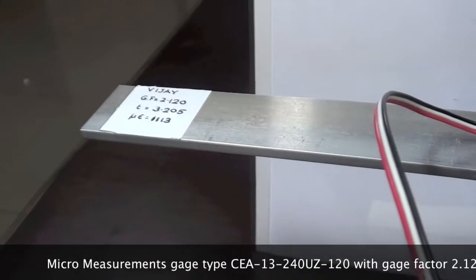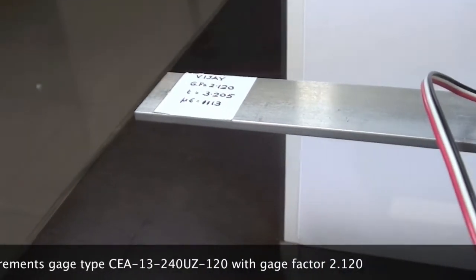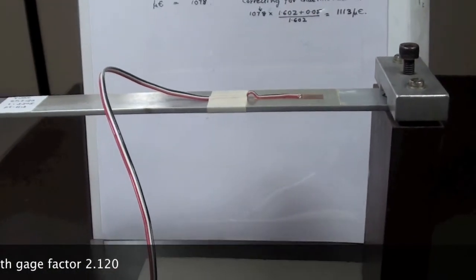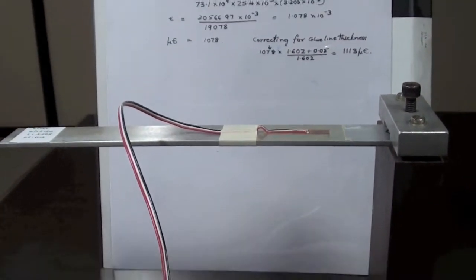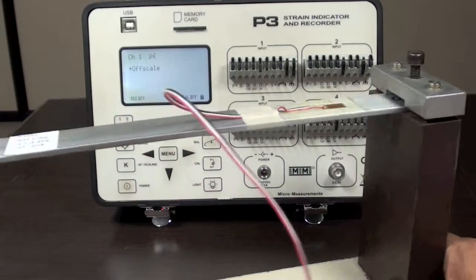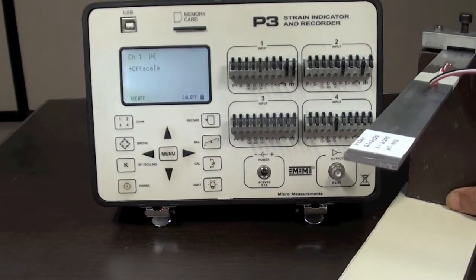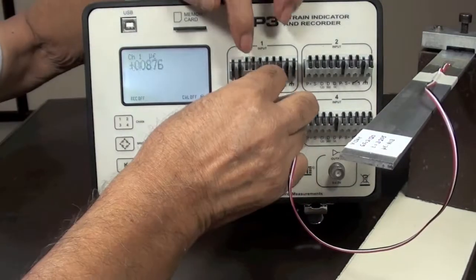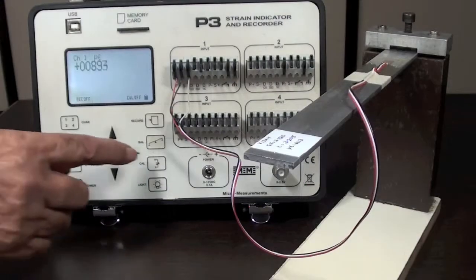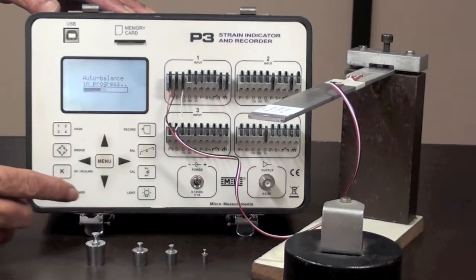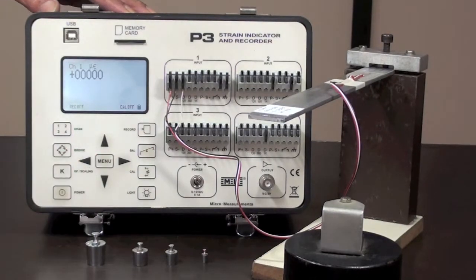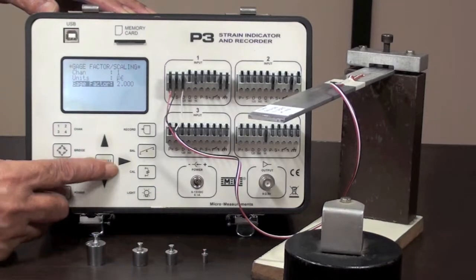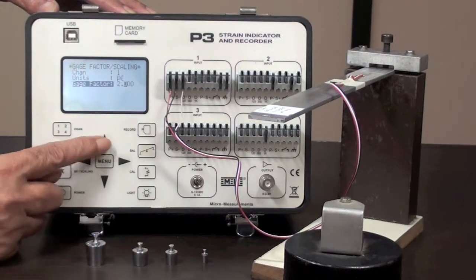A Micro-Measurements CEA type strain gauge is bonded to it and connected to a model P3 strain indicator. The gauge is balanced for no load condition and the gauge factor of the strain gauge 2.120 is set on the instrument.